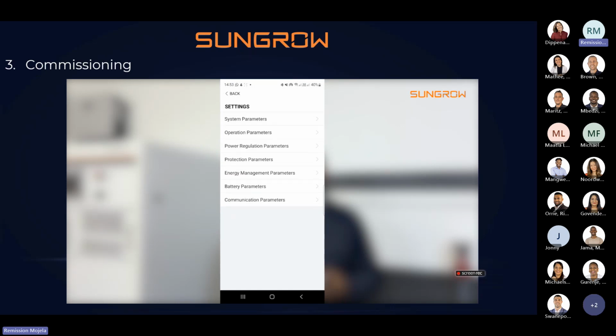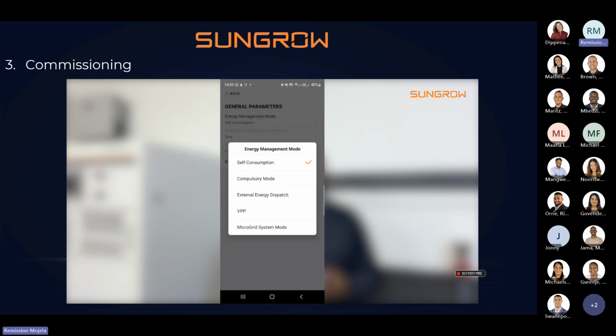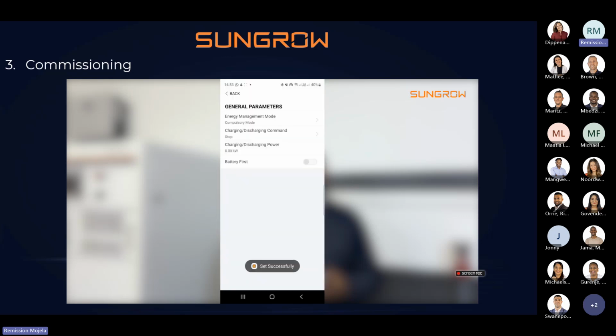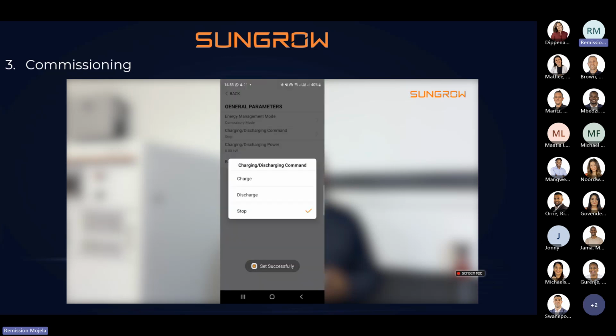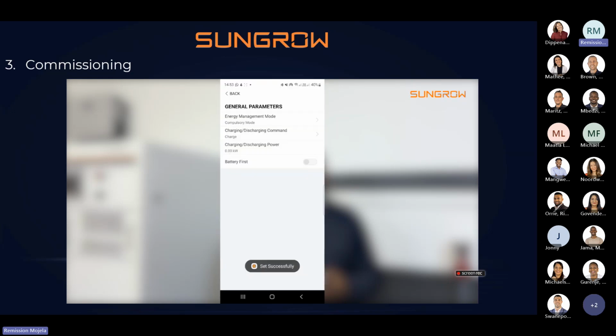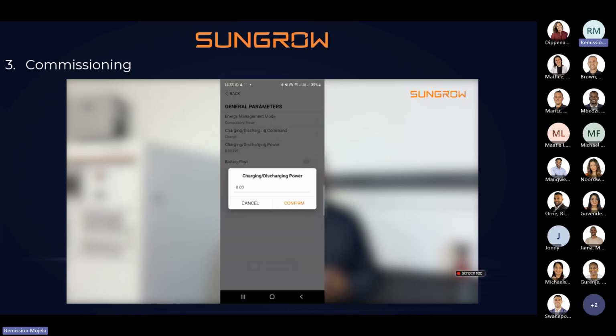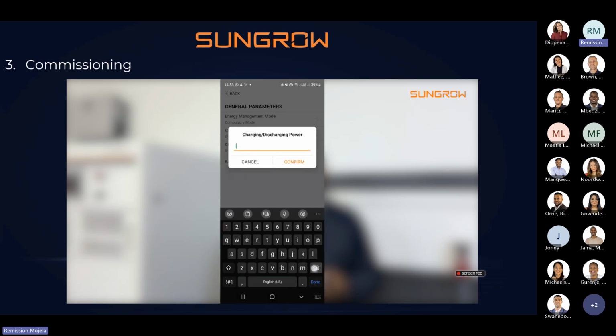Then the next thing is to select the operation mode, which is under more settings, energy management parameters, general parameters. By default, the inverter will be on self-consumption. Since this is a complete backup system, you change that: you put it on compulsory mode and set it to charge continuously. As long as there's grid, the inverter will charge. Then you tell the system how much you want to charge with.